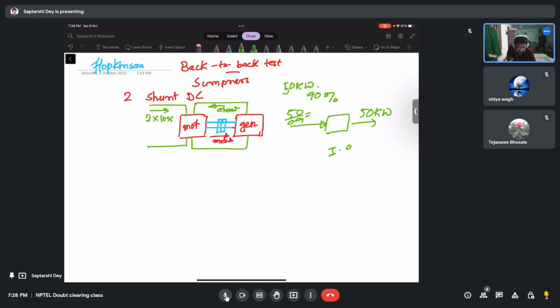10% is the loss. So 55 kilowatt of power you are drawing from the source to test one machine. But if you are doing the Hopkinson test, all you are drawing is 2 times 5, that is around 10 kilowatt of power from the source, and you are testing two 50 kilowatt machines together. Only the loss is drawn from the source. Is it clear? Two machines, one running the other, the motor running the generator, the generator running the motor, and they are drawing only the loss from the supply.